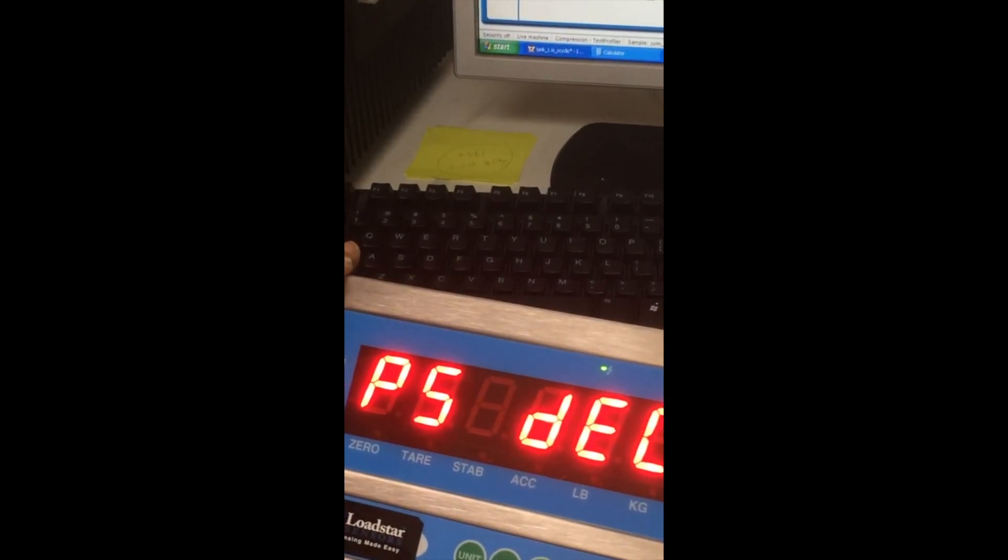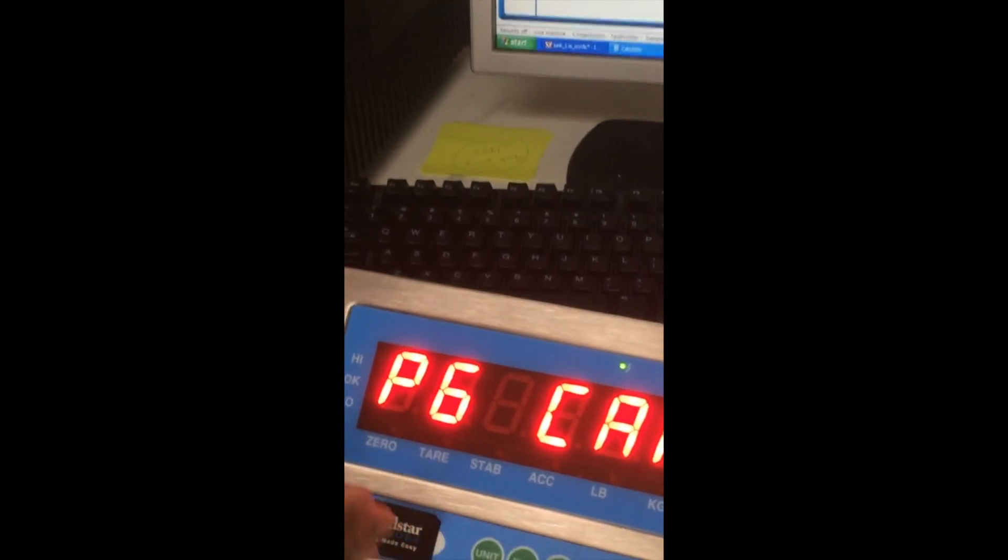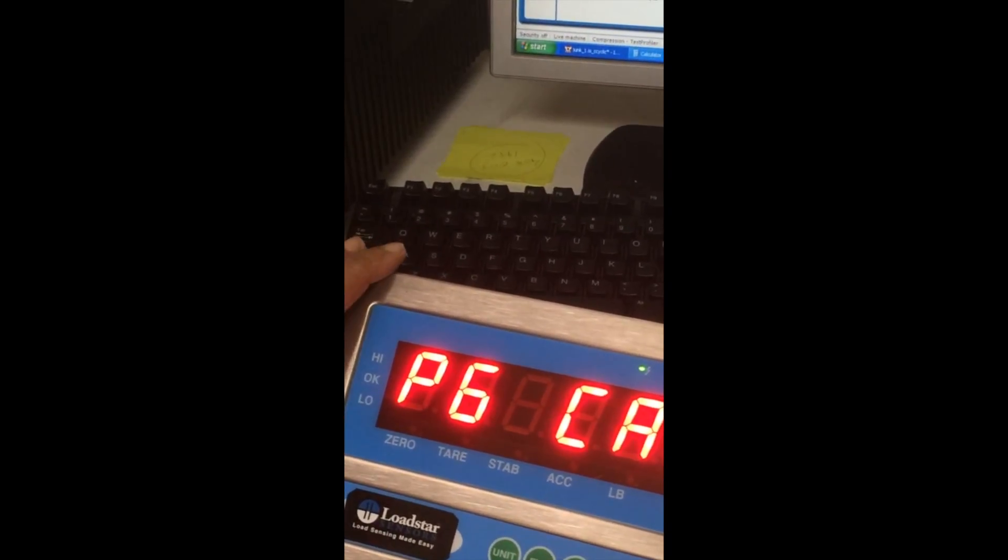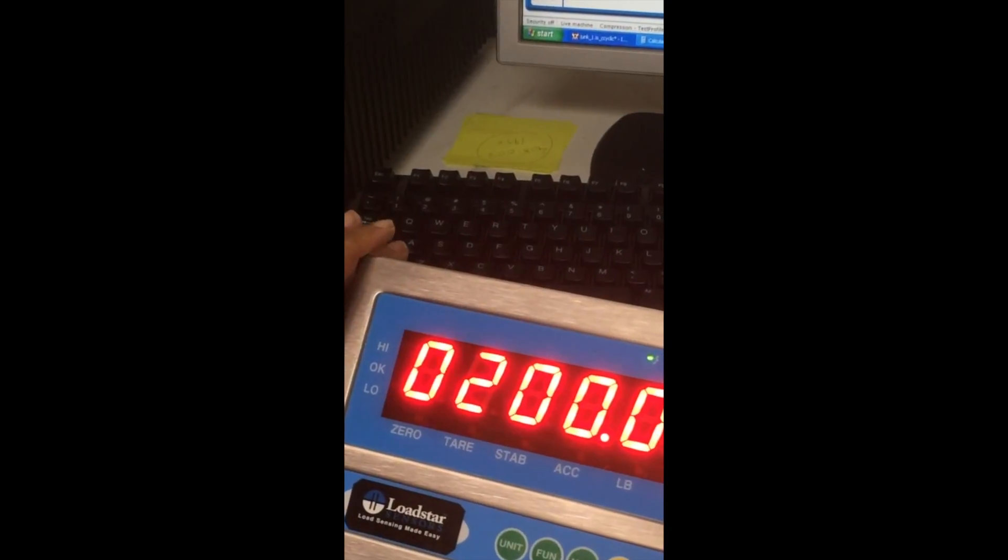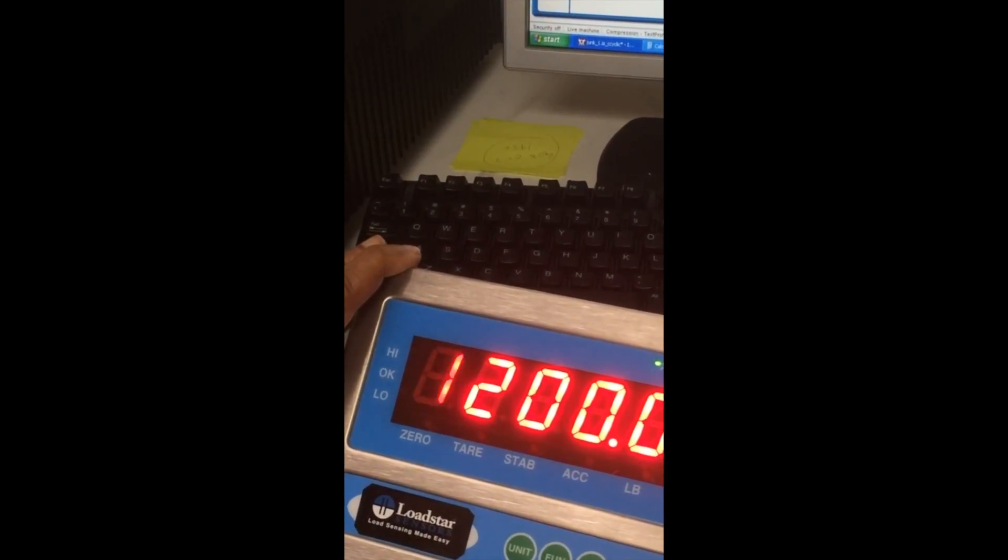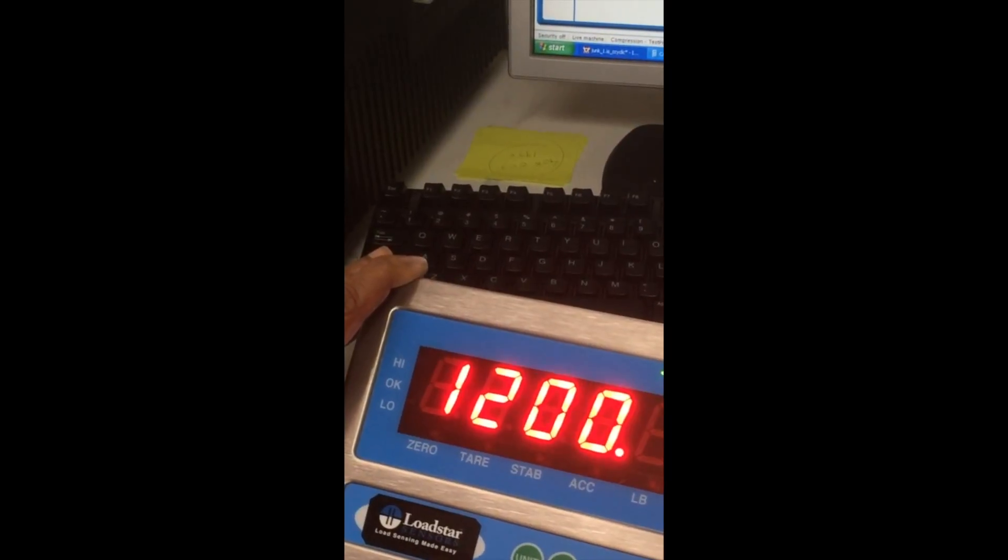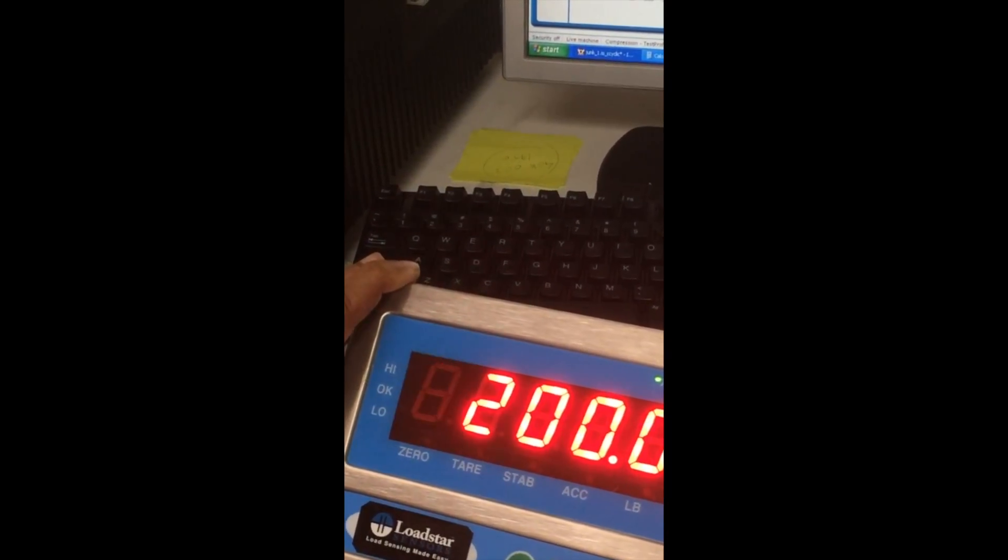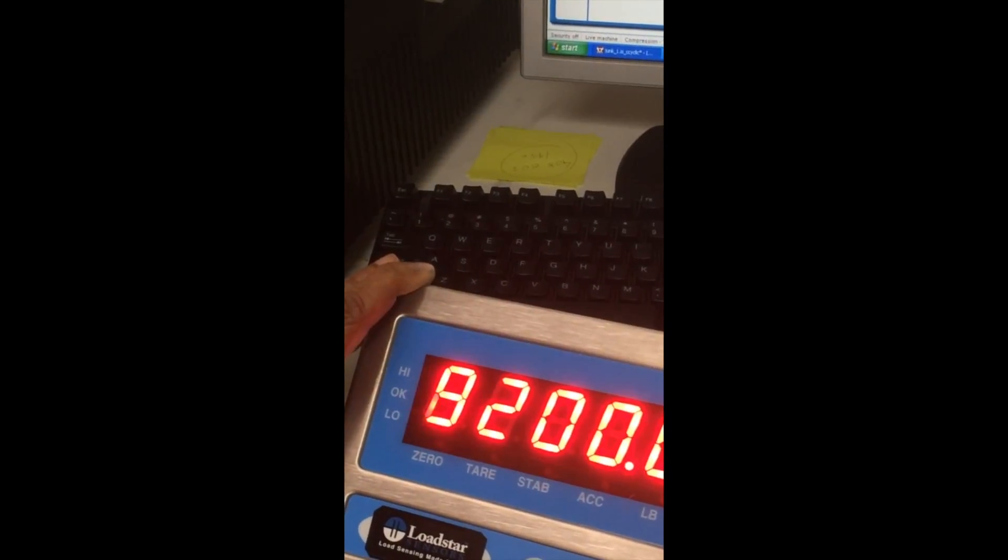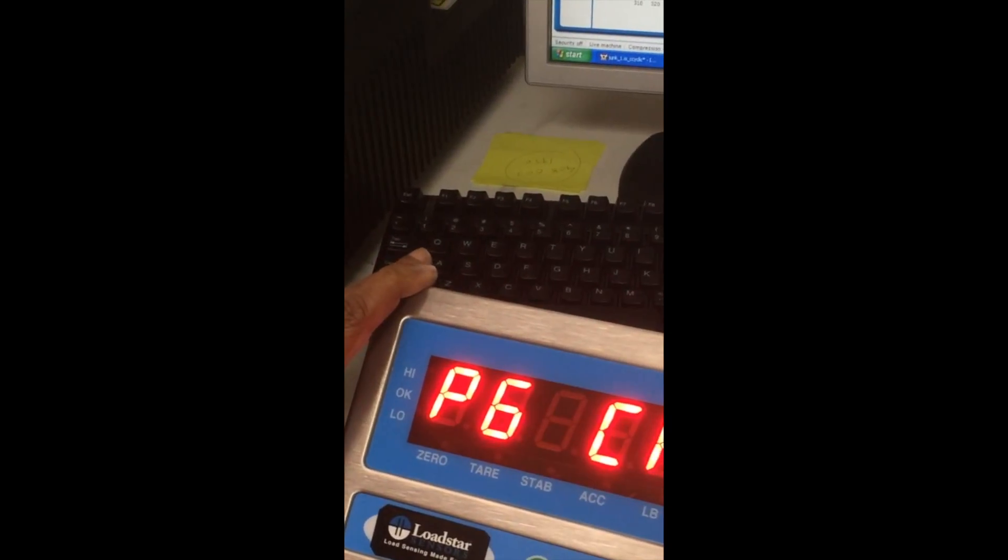Go back to go up to capacity. Here you are going to set the capacity of the load cell. This is a 200 kilogram load cell. Press the function key. You see 200. If you want, you can change it using the tare key like this and the zero key like this. And set it back to 200. Accept it. Function key.